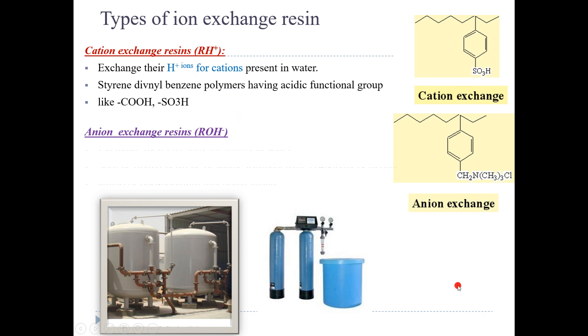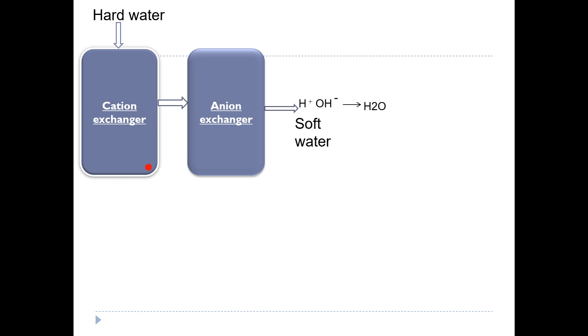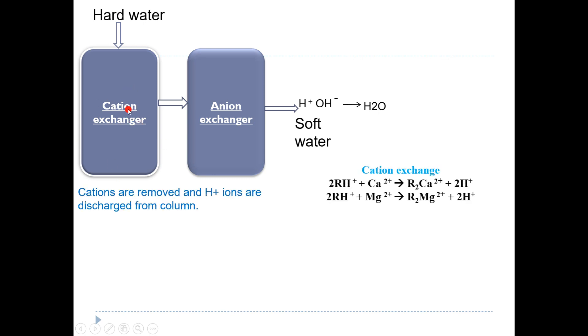In the anion exchanger or anion exchange resin, OH– ions are introduced into the water. The resin contains functional groups like amino or phosphonium, which can exchange ions. The process is two steps: first, hard water goes into the cation exchanger where exchange of cations takes place. During this first step, cations are removed and H+ ions are released into the water — the resin contains H+ ions which are replaced by the hard water cations like calcium and magnesium.